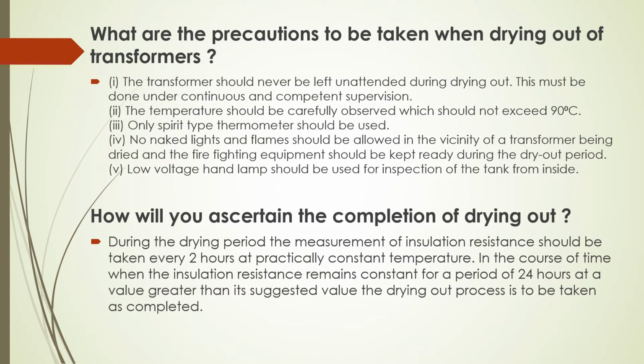What are the precautions to be taken when drying out a transformer? The transformer should never be left unattended during drying out. This must be done under continuous and competent supervision. The temperature should be carefully observed, and should not exceed 90 degrees centigrade. Only spirit type thermometer shall be used. No naked light and flame shall be allowed in the vicinity of the transformer being dried out, and firefighting equipment should be kept ready during the dry out period. A low voltage hand lamp should be used for inspection of the tank from inside.